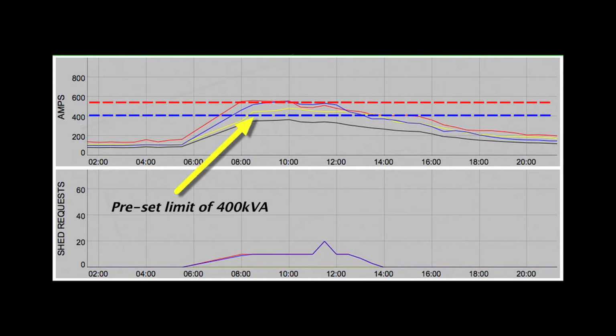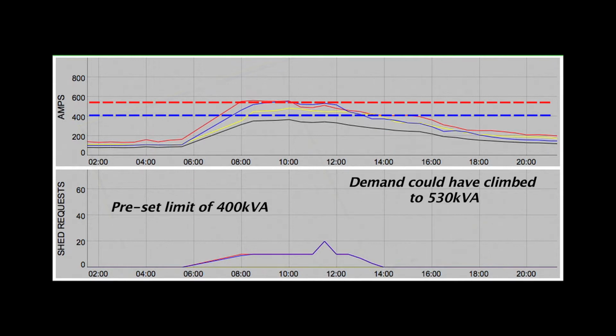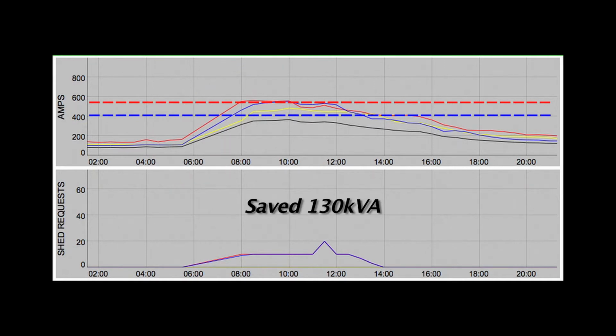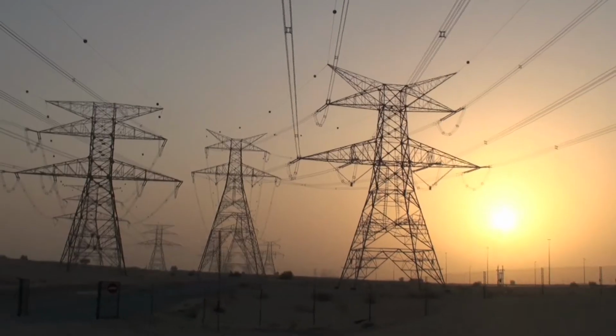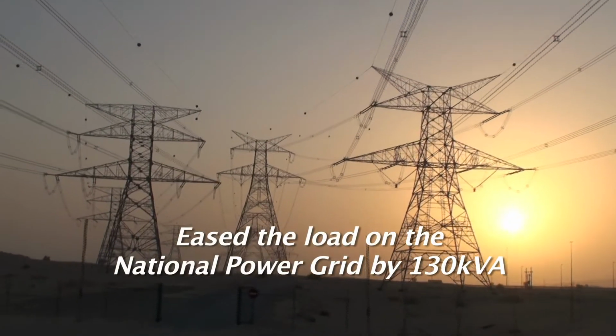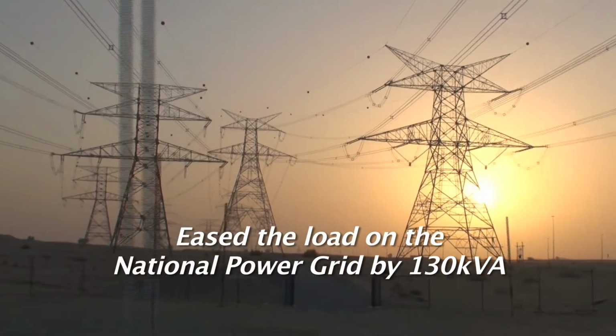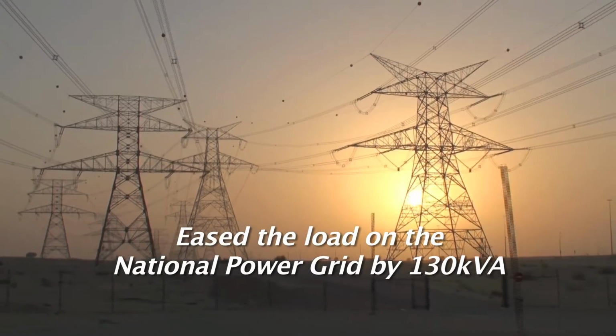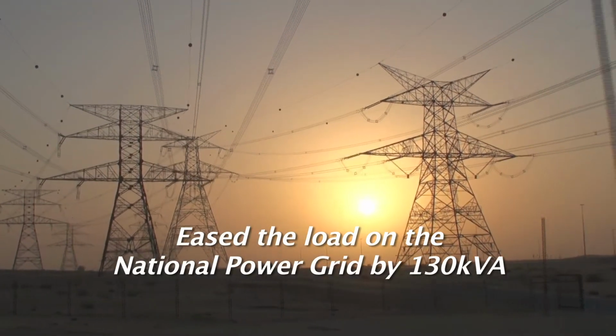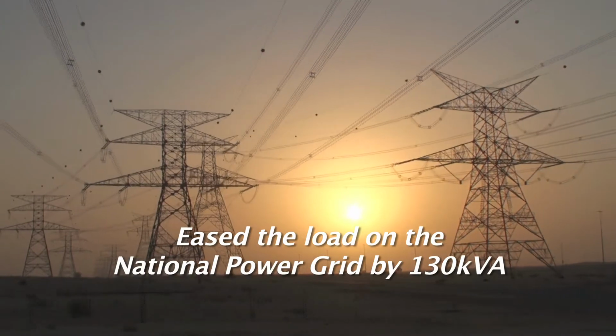But what does that mean in practical terms? Supposing PowerGuard did not intervene, the demand could easily have climbed to 530 kVA. Since PowerGuard limited the demand to 400 kVA, it saved 130 kVA. Not only did it ease the load on the national power grid by 130 kVA, but it saved the client a huge amount of money. But how much? We will see shortly.